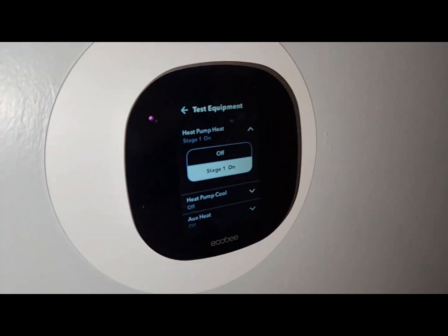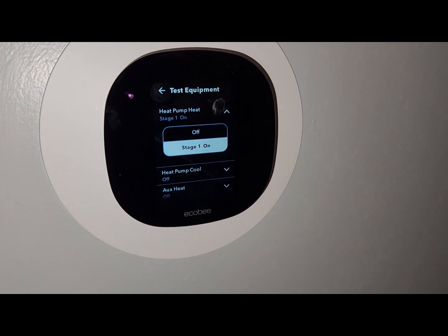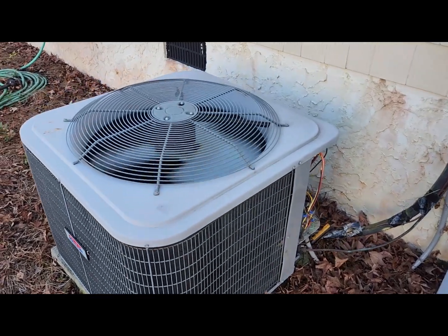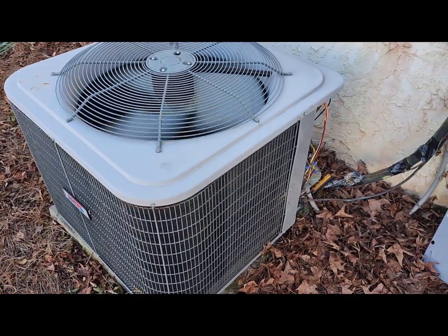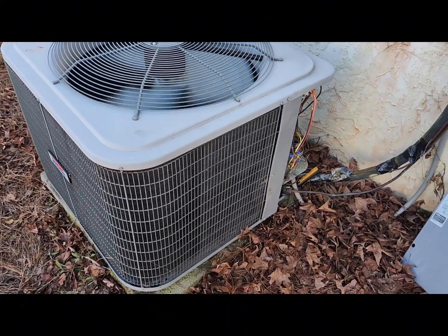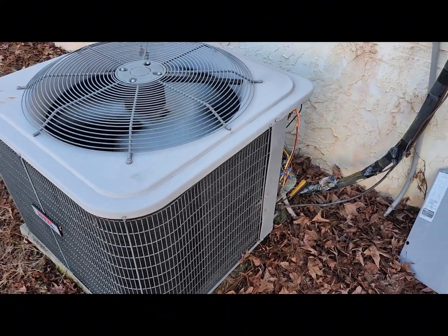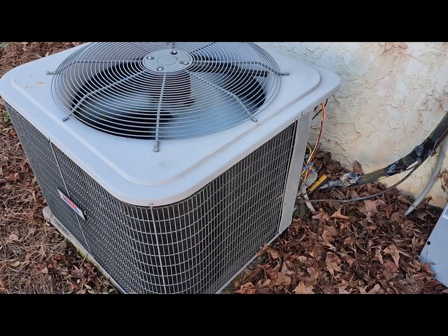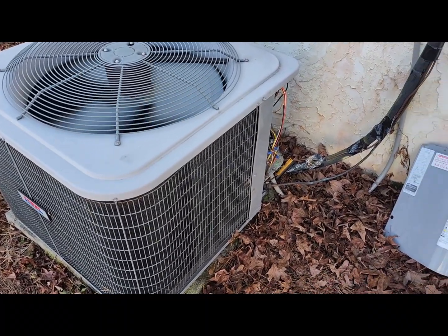We're going to put the thermostat in test mode, turn on heat pump heat, and see if that makes a difference. The unit came on — so there's something going on with that thermostat. I'm going to let it run in test and check my heating operation and airflow for the rest of my diagnostics, then go back and figure out why the unit won't come on under its own power. Then we'll have a full list of recommendations for the customer.